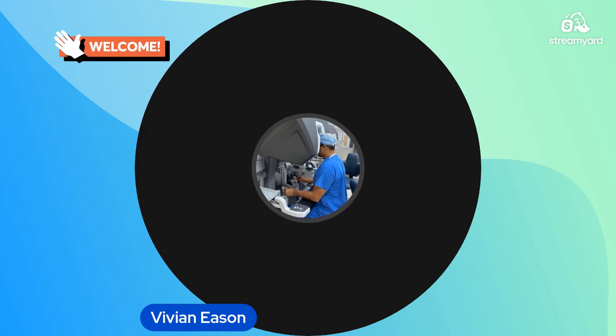After cleaning, inspection becomes one of the most important steps. The sterile processing professional should carefully inspect the instrument for cleanliness, damage, and proper function. Some important inspection areas include the working end, shaft, joints, cables, housing, and connection points. The instrument should be examined for cracks, bends, corrosion, damaged tips, missing components, loose components, excessive wear, and residual debris.